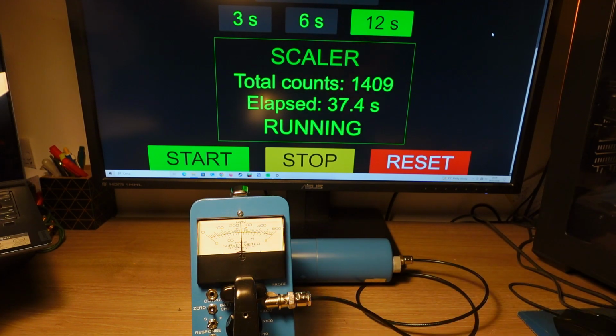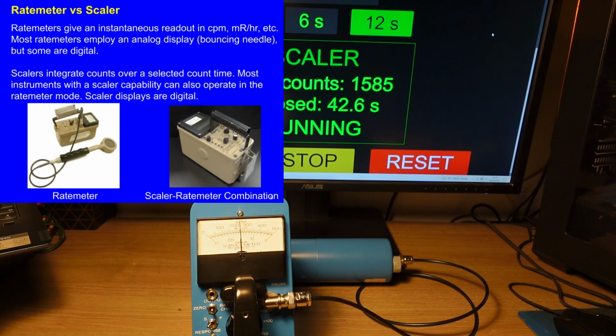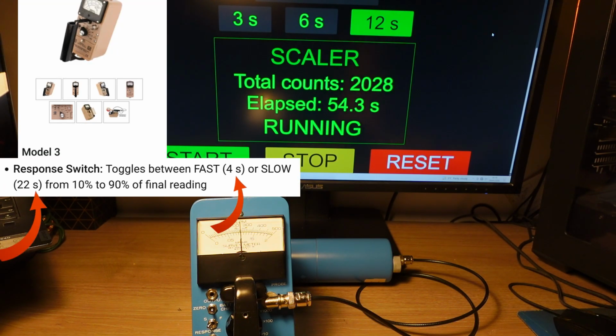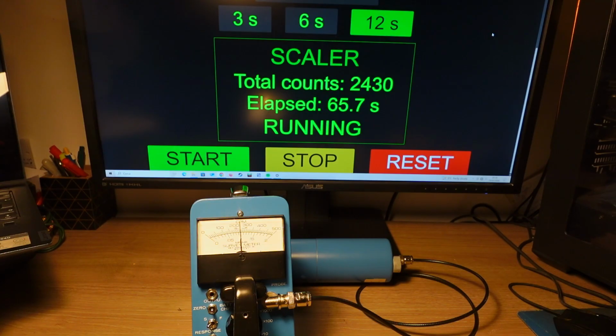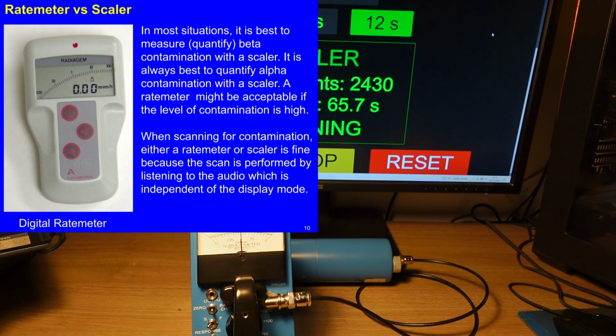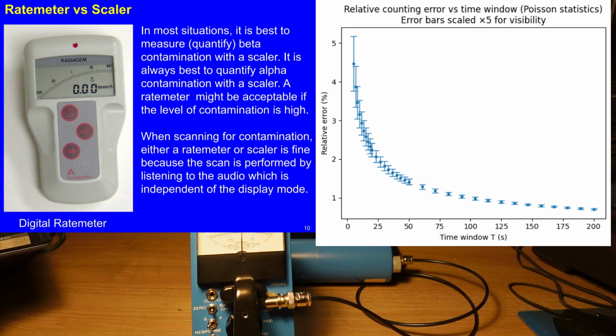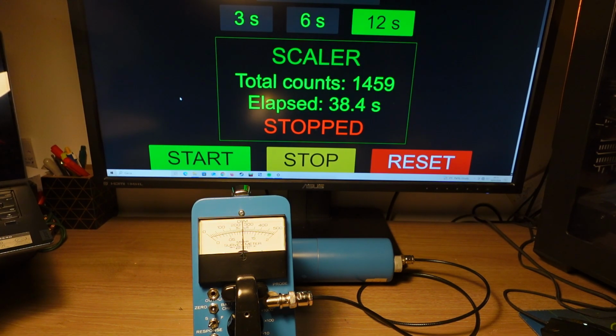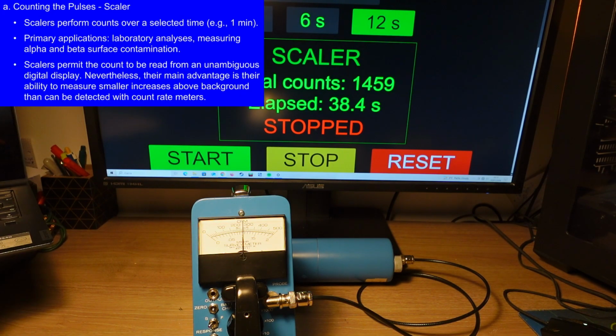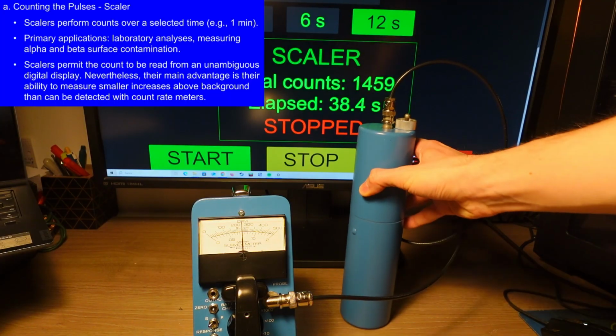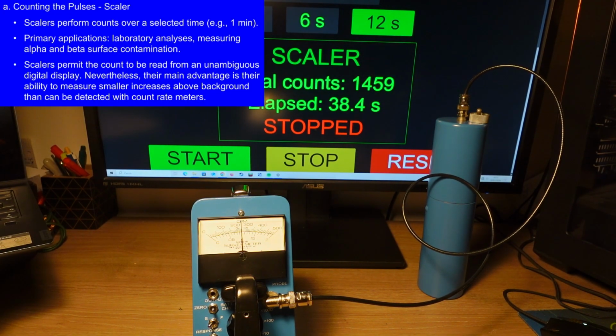With a usual meter we can just measure the instantaneous rate at which the pulses come from the radioactive decay around us. These pulses are measured over a very short time interval, for example 3 seconds or 12 seconds, but by using the scaler, so counting every pulse in an interval of time that we decide, we can have a much more precise measurement, because the error over the measurement is bigger the shorter the time window you use. Why does this matter? Because this allows us to measure contamination with the right probe. For example, if we take our probe and place it over a contaminated surface, maybe an alpha sensitive probe, we can now use the scaler to assess how badly contaminated it is.